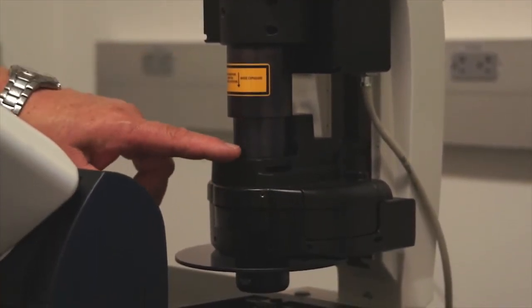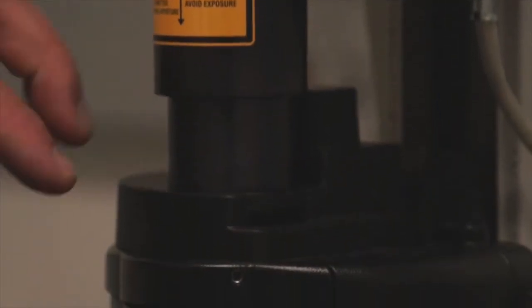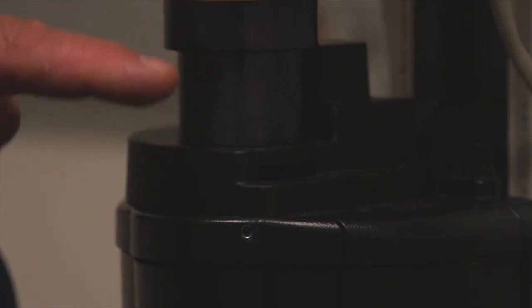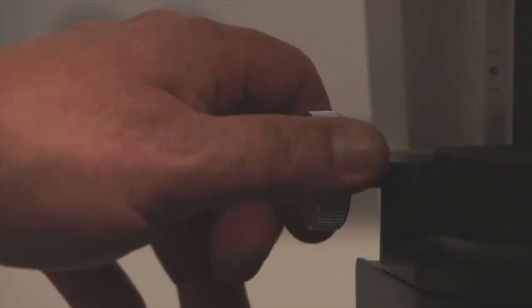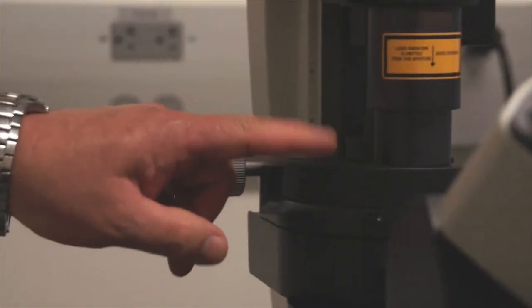Now the condenser does what we talked about previously. It condenses the light so that it goes into and through your specimen on the stage and into the optics. It is very, very important to align this condenser properly. And we will be showing you two alignment tools that go into these little slots to align the condenser in this plane. This is a knob then that allows us to raise and lower the condenser so that when we align our field diaphragm, it's nice and sharp in the field of view.